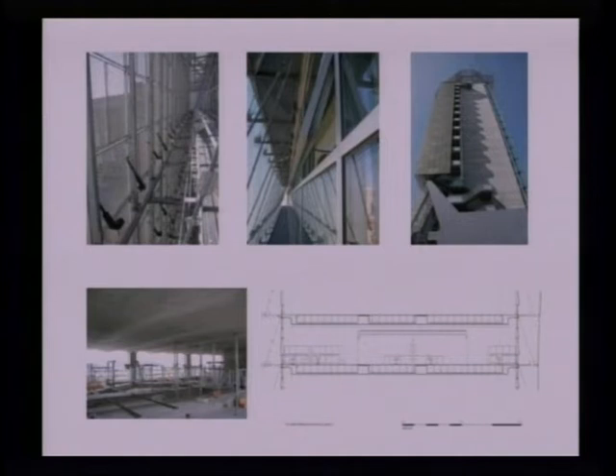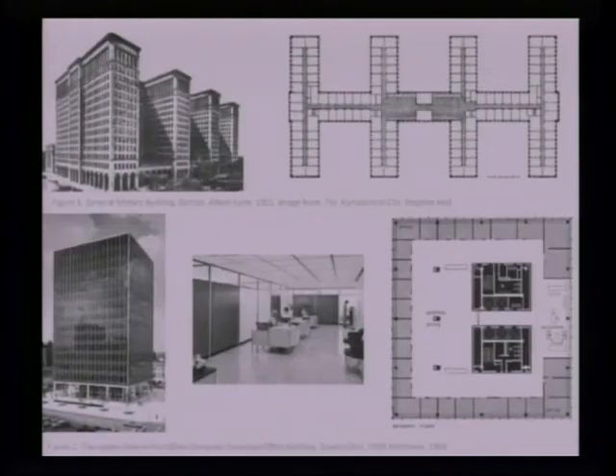So for that system to work, the building had to provide adequate solar control to avoid overheating of the structure. Solar control could also be considered for overheating of the occupants working along the perimeter. But in this case, it was based on a large scale look at the energy modeling implications of having direct beam hitting that structure without any solar control. That night flush cooling wouldn't be capable of rejecting those heat gains for periods of the year. So these facade systems were developed both to control loads on occupants, but also to make sure that cooling strategy would work.